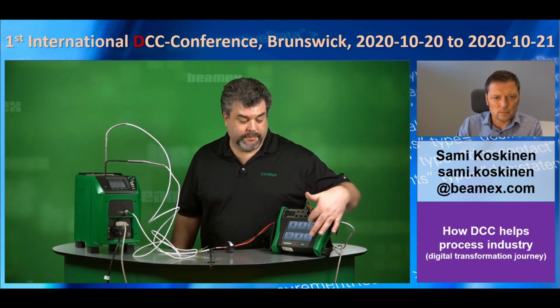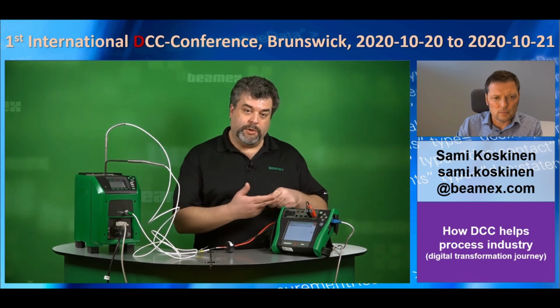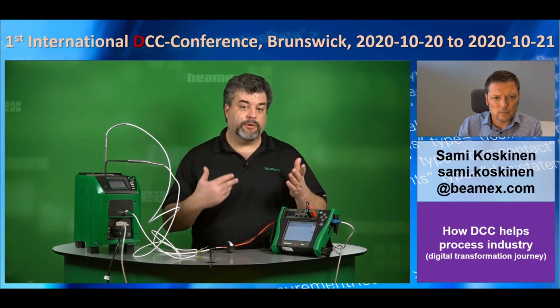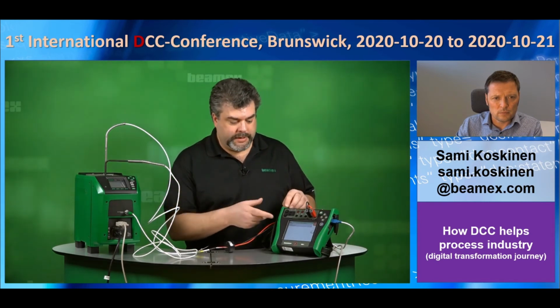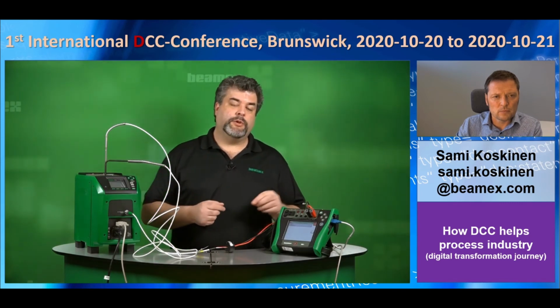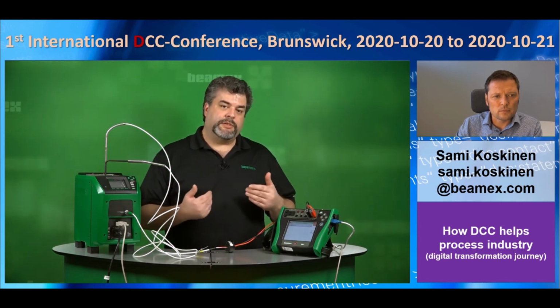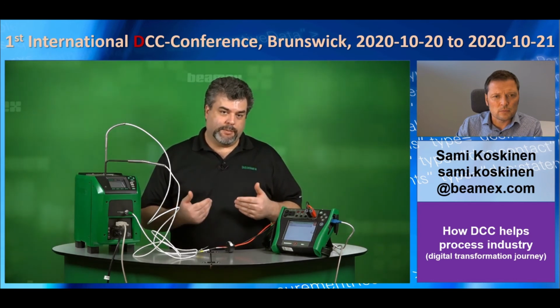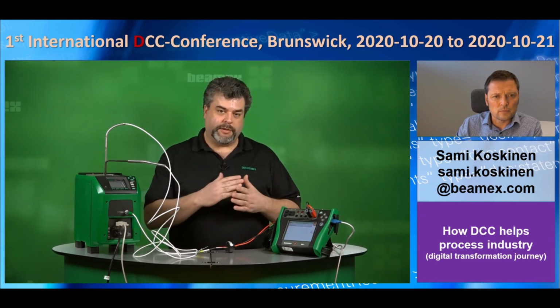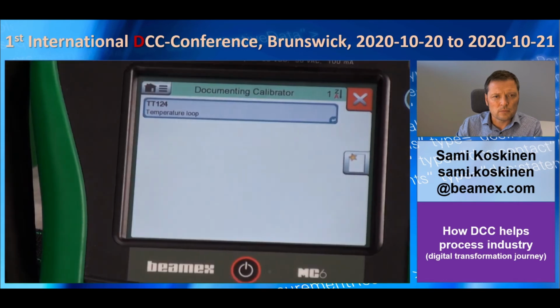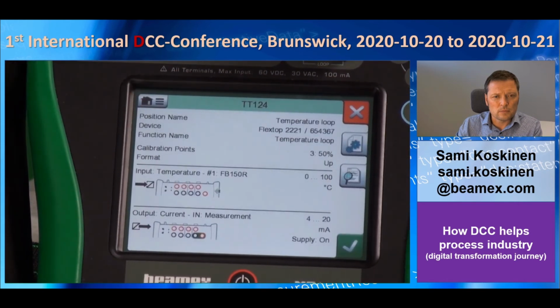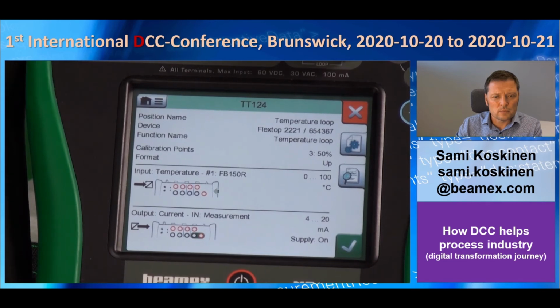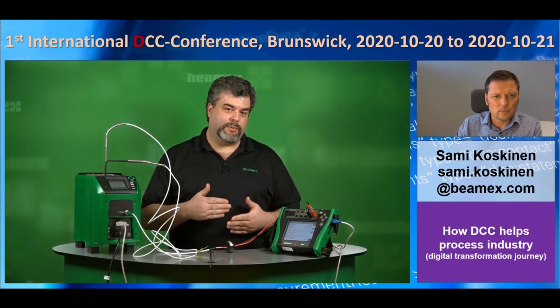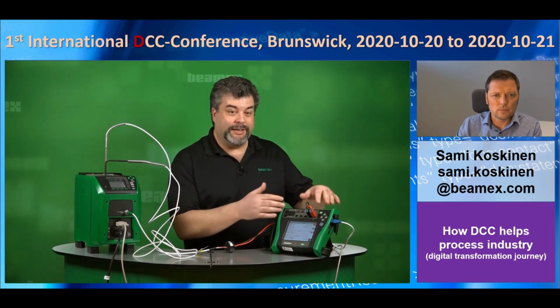Documenting calibrator. You see the list of what you have due for the day, or maybe what's due for your shift. In this case, I have one. It's position TT124. Just before this, I brought it over using CMX, our calibration software, so everything was loaded up with all the critical details. As a technician, I simply touch on the instrument. This gives me a rundown of what I'm doing. It tells me what the instrument name is, what the function is, what the input and output parameters are, and it even tells me where to plug in.